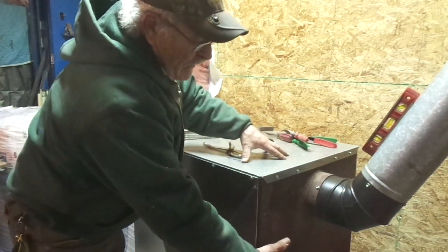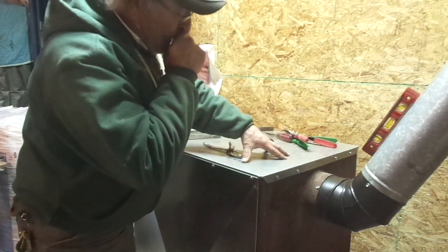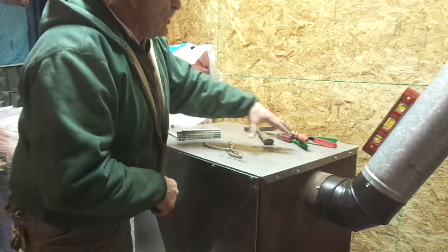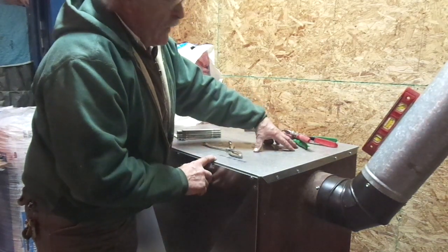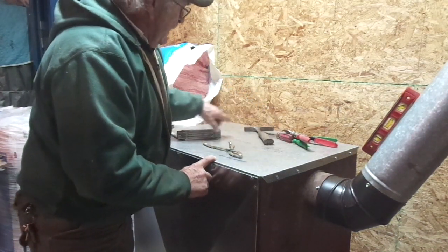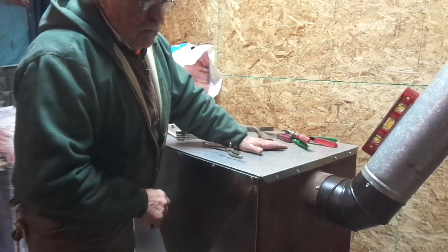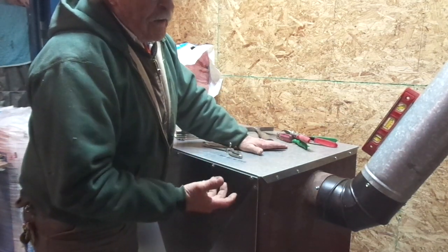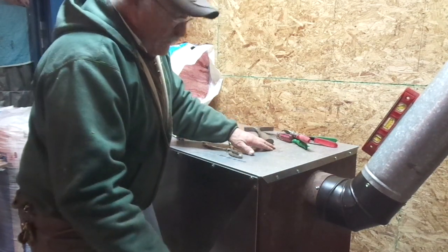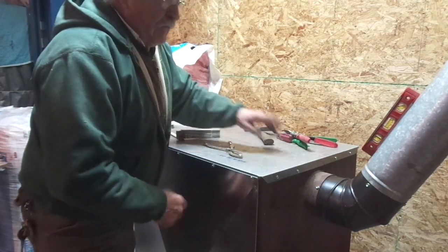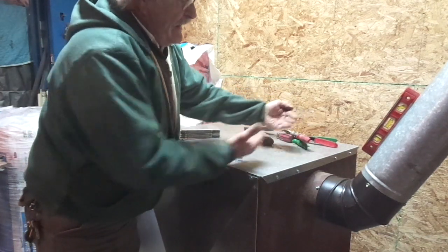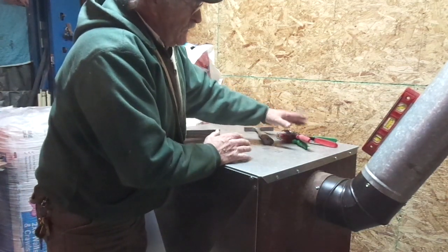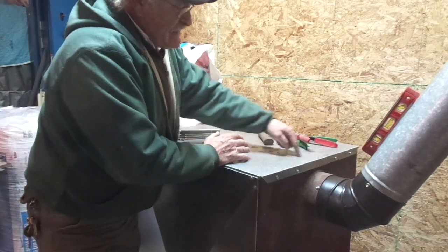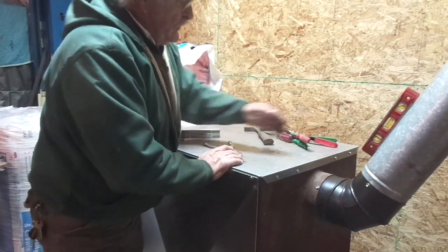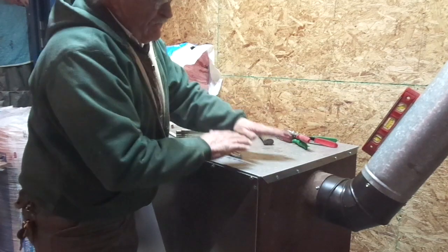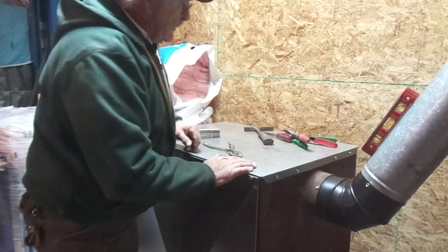You're going to get the majority of your air off that heat exchanger coming up from back here and that one side. So I'd have a tendency to believe you'd want to put them towards the center. Now bear in mind, this is temporary. Ultimately this will become installed somewhere with ductwork attached to it. So I'm going to put these in the center for two reasons. First, I believe I'll get a mixture of air from both sides of the heat exchanger. Plus I'll be able to easily adapt those two round holes into a rectangular opening whenever I want to add a flanged fitting for a plenum and then ductwork coming off of it.